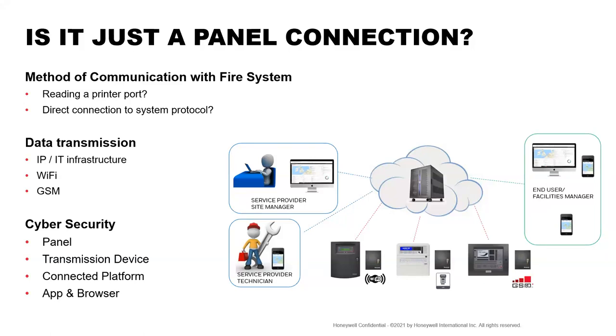So is it just a panel connection? Well, when we look at how we're to connect to the fire system, we need to understand which method would be best for the extraction of the detailed information that we're trying to get out. We've got a connection via the panel's printer port output. This will give rudimentary info that's displayed when the fire system does something, i.e. a fire condition or a fault condition or an isolation or a disablement if somebody isolates a detection.